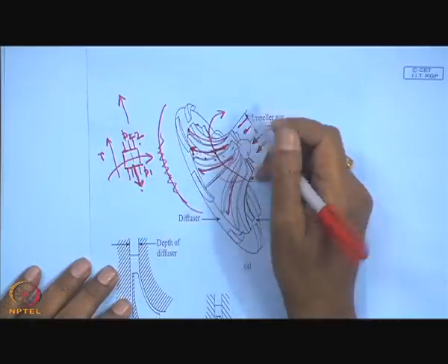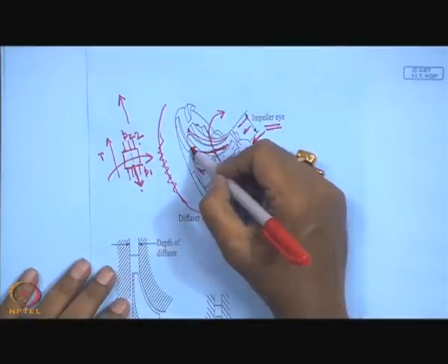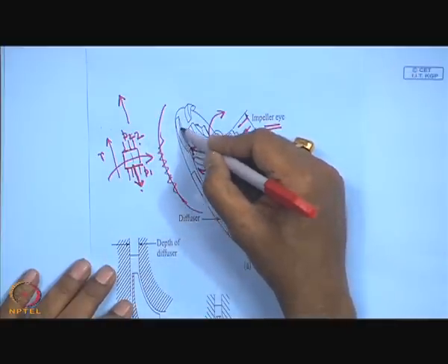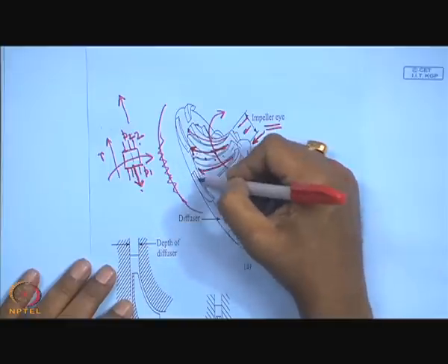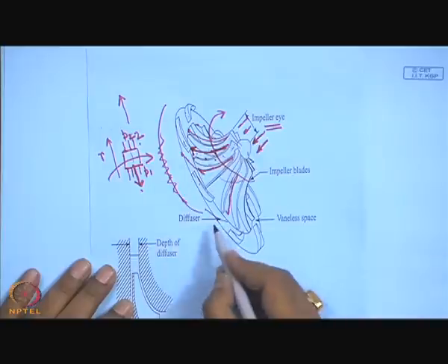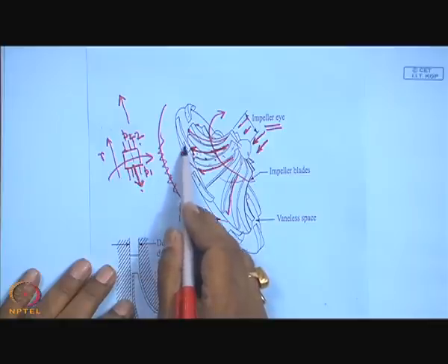The air has a high velocity, and at the same time it has a high pressure, but we want more pressure and less velocity. So, what happens? It goes through some stationary passages made by these vanes. These are stationary vanes, and this is known as the diffuser. This passage is known as the diffuser. So, you see it is written, this is the diffuser, where, when the flow takes place, there is no energy exchange, only the fluid flows in a direction where the area increases.